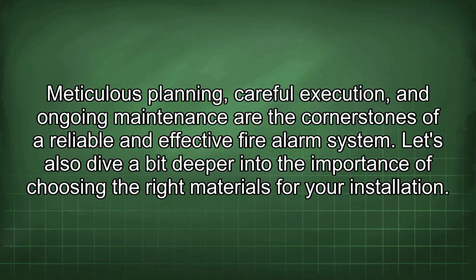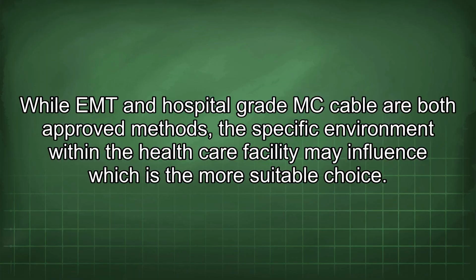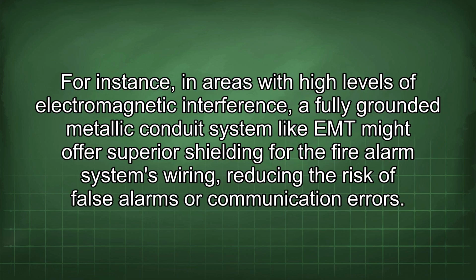Let's also dive a bit deeper into the importance of choosing the right materials for your installation. While EMT and hospital-grade MC cable are both approved methods, the specific environment within the healthcare facility may influence which is the more suitable choice. For instance, in areas with high levels of electromagnetic interference, a fully grounded metallic conduit system like EMT might offer superior shielding for the fire alarm system's wiring, reducing the risk of false alarms or communication errors.